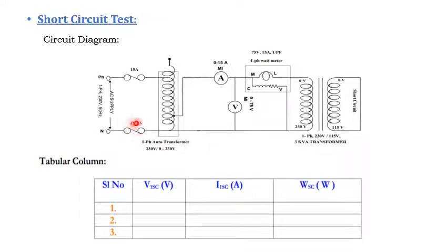Similarly here, a reduced voltage is given, reduced voltage in the sense of what, with respect to the current. So what is the rated current of the transformer? With respect to the rated current of the transformer, the supply is given here. To that extent, note down the voltmeter reading and the wattmeter reading, which gives the short circuit voltage, short circuit current, and short circuit power. It is nothing but the copper loss. So this is about the short circuit test.